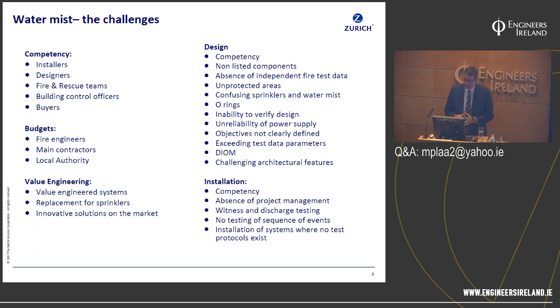And moving on to installation, again, competency of installers is a key concern for insurers, but also, as with the wider construction industry, absence of project management. We often find that these systems are simply given to a subcontractor, or a subcontractor subcontracts to someone else, and there is no verification of that installation on site by the supplier, the installer or a third party. So they're simply left to their own devices to install the system. And guess what? It's not surprising we find problems on site. I go along and snag and find multiple issues and leave the client with a big long list of risk improvement actions because that system is simply not fit for purpose. I shouldn't have to police the industry, but I'm doing that quite often.